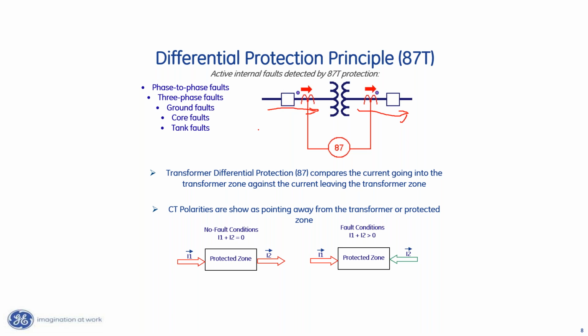If I have a fault here, I could have current flowing here to ground, or between the phases. And I could have it flowing here, right? Now, if that's the case, then I'm in this situation. So I've got current flowing into the zone of protection. Current on the left flowing into the zone of protection, that's 10 at 0 degrees. Current on the right flowing into the zone of protection, that's 10 at 0 degrees. That's 20 at 0 degrees. So that is differential current that looks like a fault.